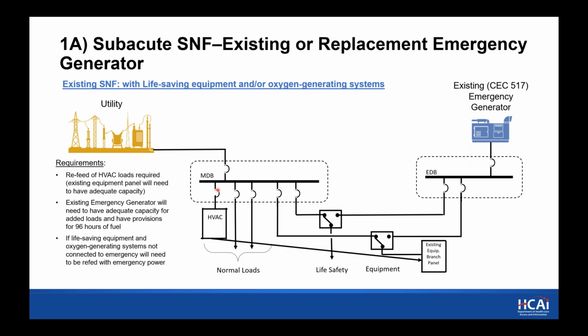If there is life-saving equipment or oxygen generating equipment that's not connected to the emergency system, this would need to be refed with emergency power. And again, this option is if you have capacity on your existing generator, or if you replace it with a larger capacity generator. Thank you.